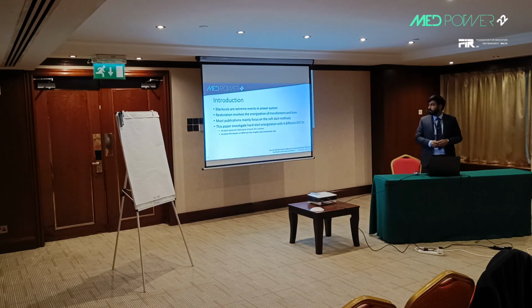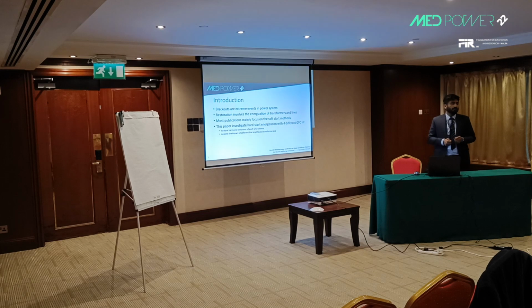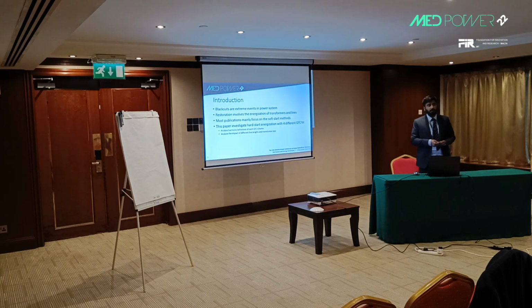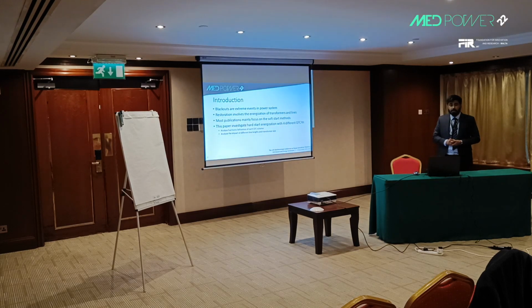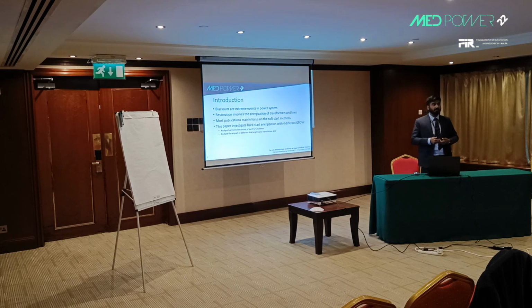Therefore, this paper focuses on hard energization using four different kinds of grid-forming converter topologies. We investigate the energization of transformers, which is the main issue in the energization process because it requires a lot of inrush current when energizing, and how this interaction between converter and transformer occurs, and how different line lengths and transformer sizes affect these interactions.